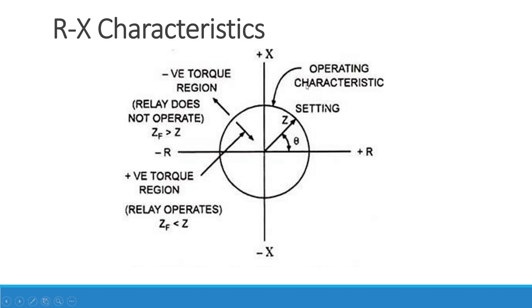When converting from the VI characteristics to the RX characteristics — the RX plane — for the same slope on the VI characteristics you get a circle with the radius equal to Z, which is the setting impedance. Inside the circle you have the positive torque region where the fault impedance is less than the setting impedance Z, and the negative torque region is outside the circle where the fault impedance is greater than Z. When a fault occurs outside the circle the relay will not operate, and when the fault occurs within the circle the relay will operate.